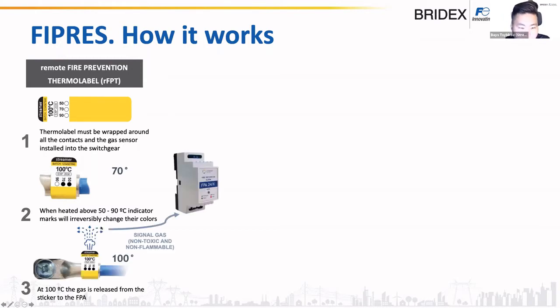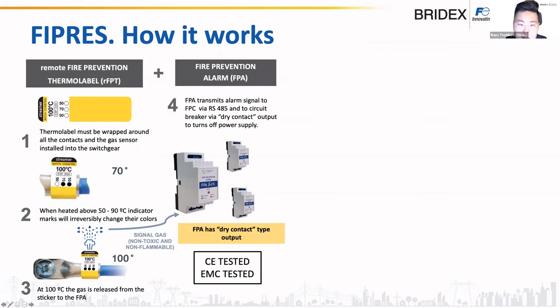So when the contact is heated up to the activation temperature of the sticker, which is 100 degrees, you can see it here. The gas from the yellow part, which is encapsulated there, starts to be released from the sticker inside the switchgear. So it spreads inside, and the concentration of this signal gas rises, and this signal gas is detected by the FPA. FPA is a fire prevention alarm. So the FPA detects the gas, it generates an alarm signal that something went wrong, and it sends this signal via Modbus to the monitoring or BMS system, or via a dry contact output, which is a discrete relay. You can connect it to a buzzer or a lamp or a local fire alarm system.